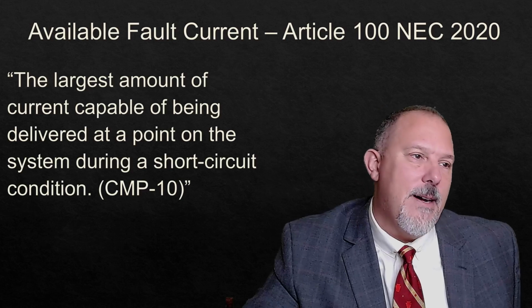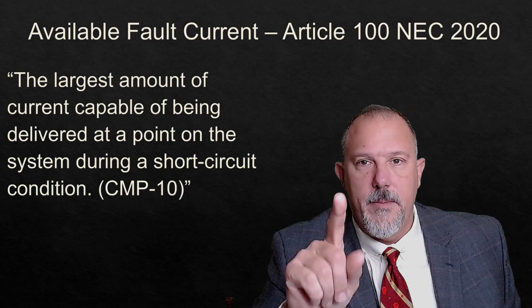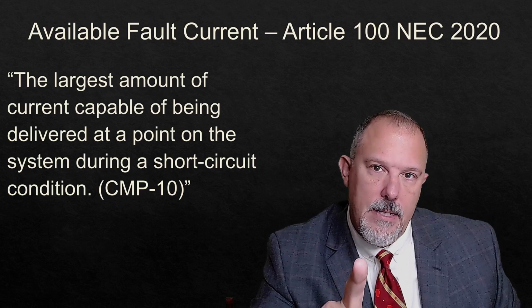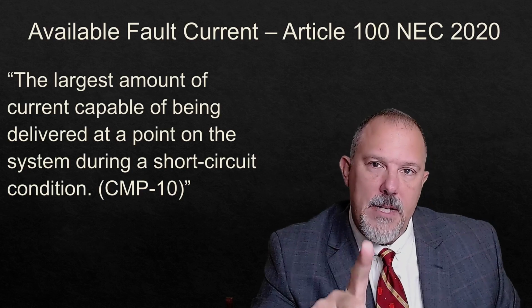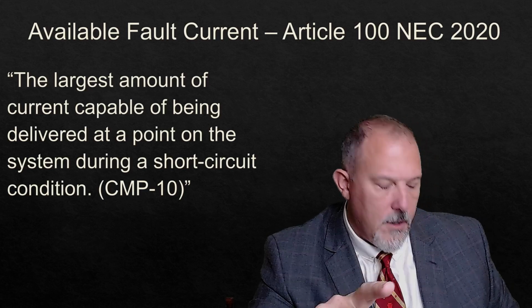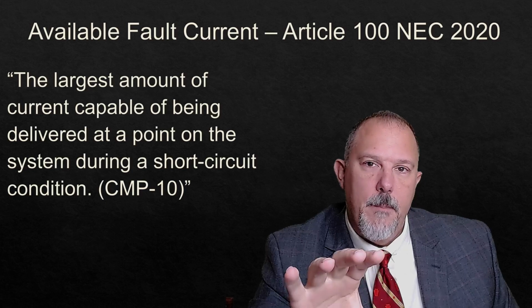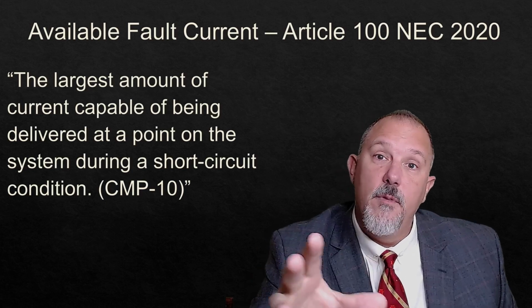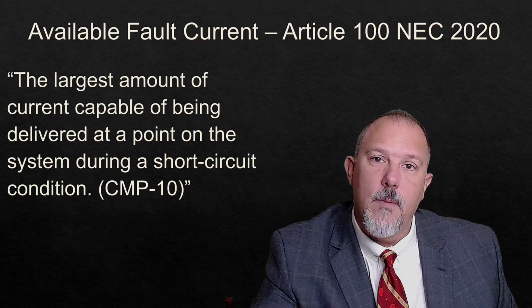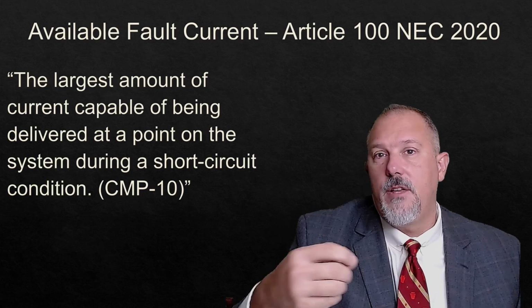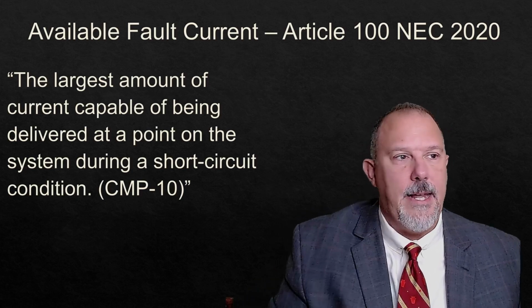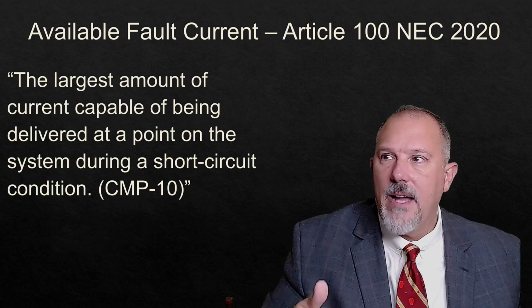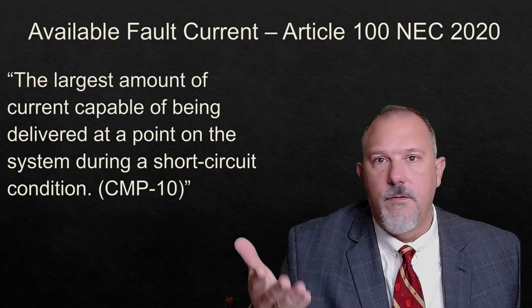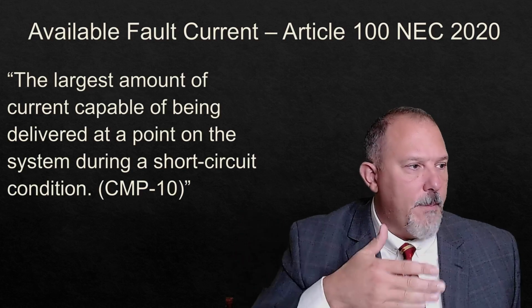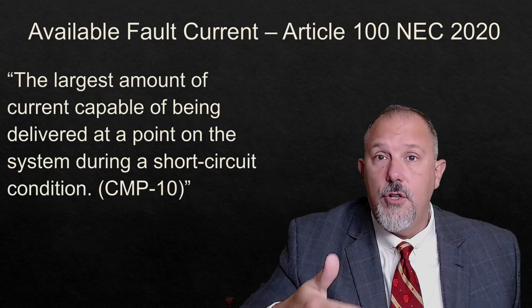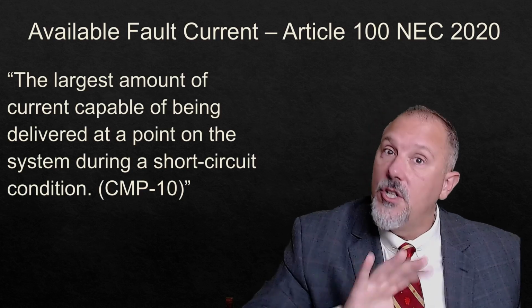Now why is 110.9? Why didn't we see the word maximum in there? Just remember what 110.9 tells us. An interrupting rating for a device may not be associated with an available fault current. I might have an interrupting rating because that piece of equipment is only intended to, say, interrupt load currents. So I'll have a maximum interrupting rating of, say, a contactor of some sort, that it doesn't have an interrupting rating from fault current, but it does give you the maximum amount of current that it can stop from flowing, which is not a fault current.